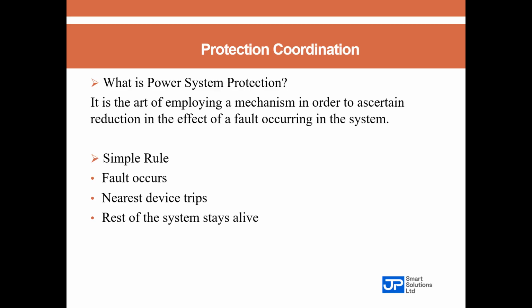Now, let me share a story. One of our clients had a 33 by 11 kV industrial substation, and every time a fault occurred on a single feeder, the entire 33 kV bus tripped. So we were consulted, and when we ran a coordination study in ETAP software, it was obvious. Their relay settings overlapped, which caused upstream relays to operate first. Now, after correction, faults were cleared selectively and downtime dropped by 70%. This is the power of proper coordination.